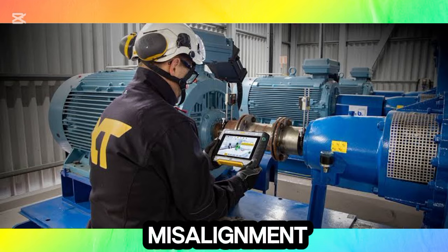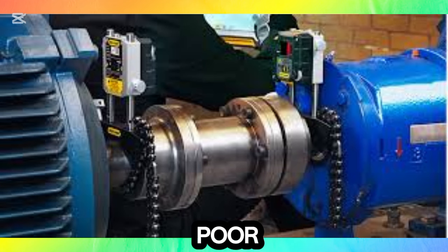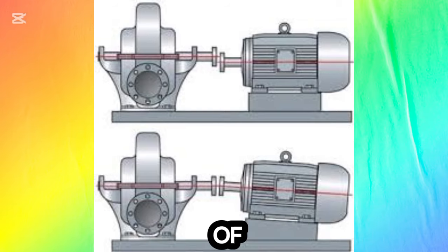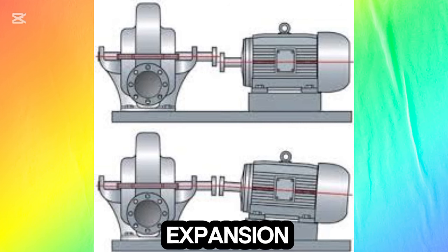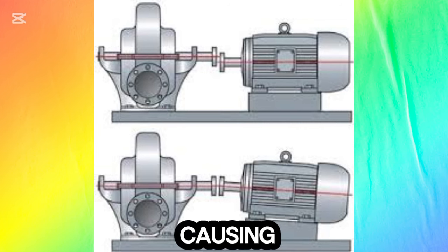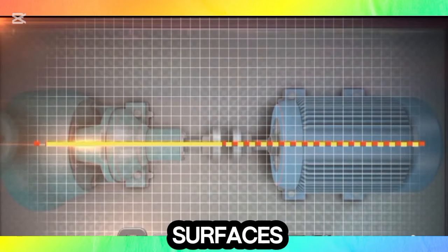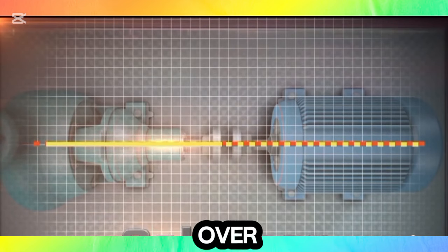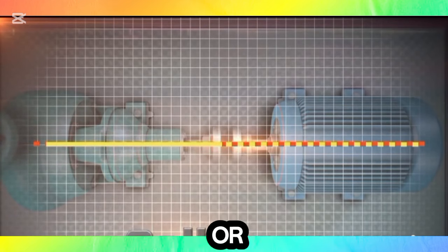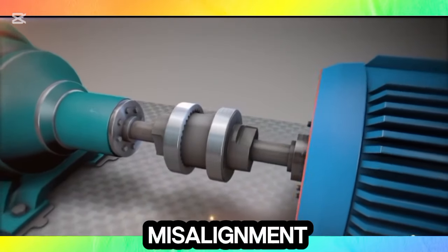Causes of misalignment: improper installation, poor alignment during installation of the motor and pump; thermal expansion, temperature changes causing components to expand or contract, shifting alignment; foundation issues, settling of the base or uneven mounting surfaces; wear and tear. Over time, loosened bolts or worn couplings can lead to misalignment.